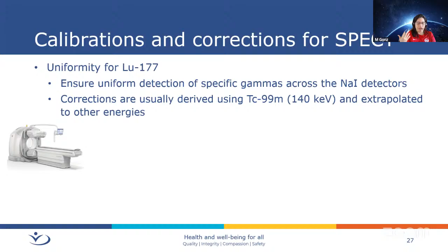So we had to check for all of those 20 plus cameras across the province: are they performing okay, so that if we image at the lutetium energies, it's still a uniform response, the correct response. To give you a quick example, this is what the spectrum of lutetium-177 looks like on those sodium iodide cameras. This is the 208 peak, and that's the 113 peak. The cameras are calibrated for 140, so they are calibrated in between those two. But are those calibrations good?